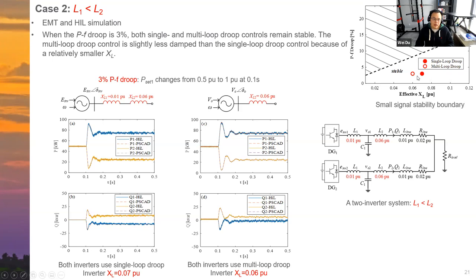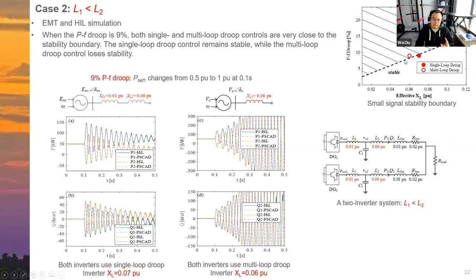stability boundary map, right? If we keep increasing the droop gain from 3% to 9%, then we start to see some difference. You can see both of them are much less damped, but the CERTS droop control is still stable because it's very close to the boundary, but below it, so it's still stable. But for the multi-loop droop control, it's higher than the boundary. That's why it loses stability. So again, this kind of small signal analysis and simulation helps provide insight into the design philosophy of these two controls and helps people understand how we should design grid forming inverter controls.